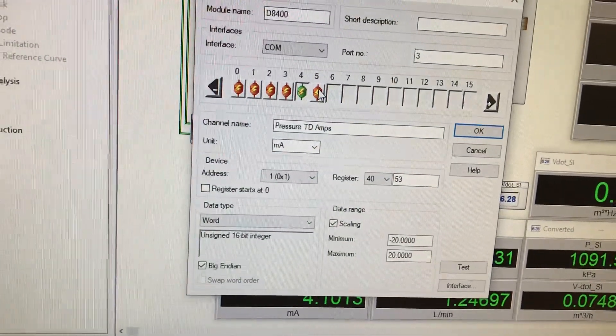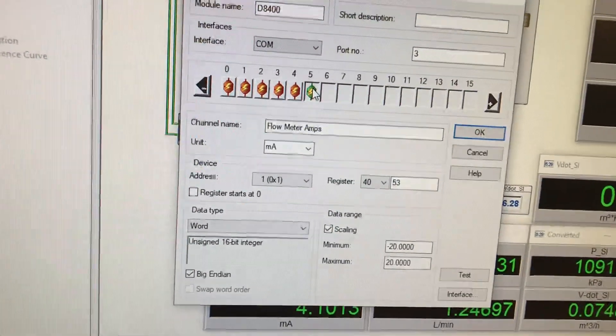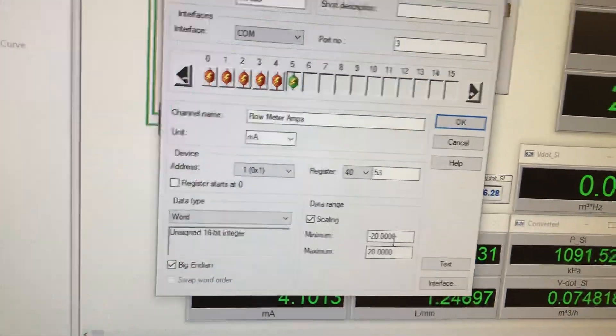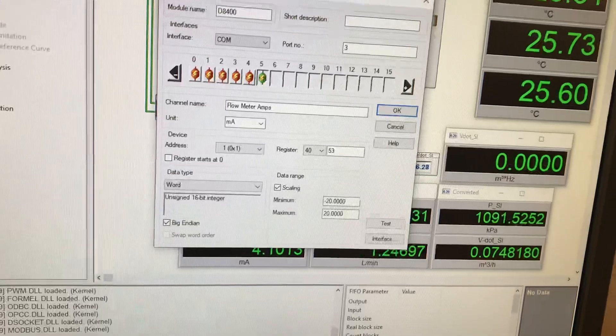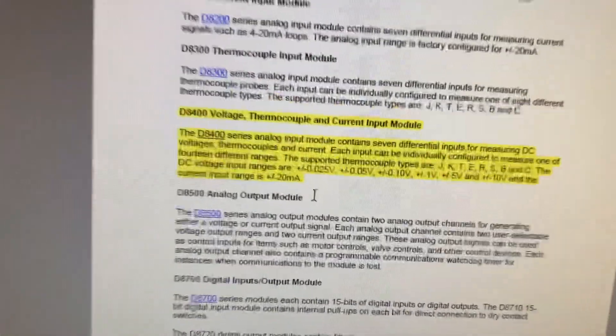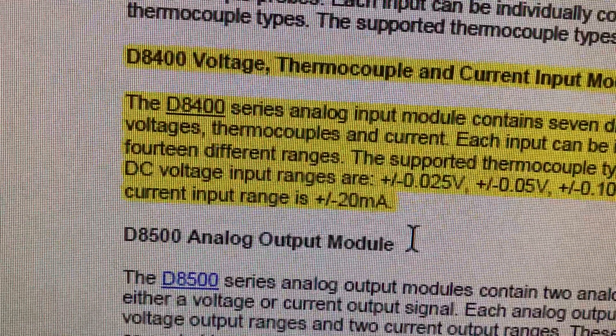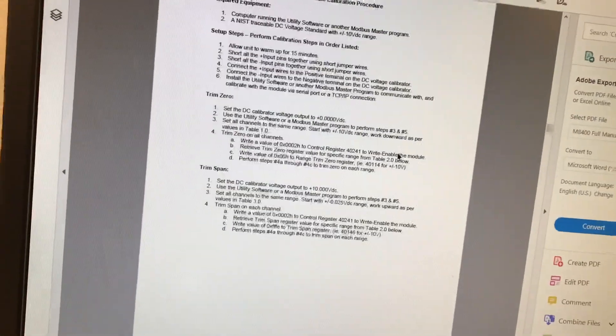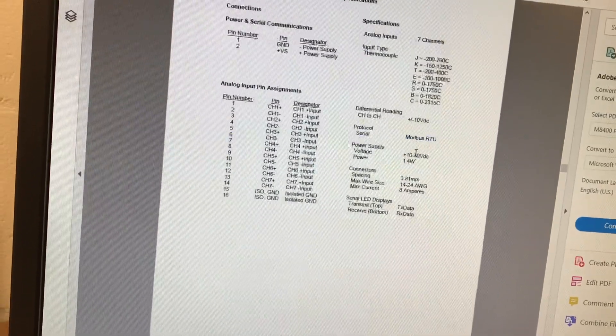So I guess we'll go to the scaling first. If we go over to the current channels, we've got pressure transducer milliamps and flow meter milliamps with a minus to positive 20 milliamps scaling. Let me show you why that is. The current range is plus or minus 20 milliamps, so that's why the scaling you see there is there.